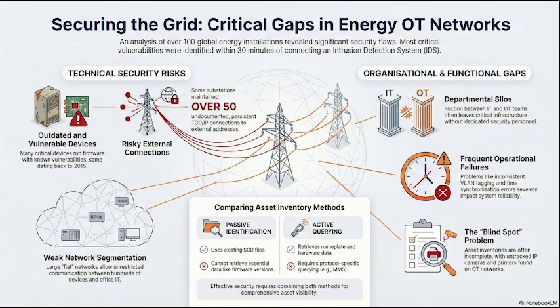If a blackout happens, you need to know the exact sequence of events: device A tripped at this millisecond, device B tripped 3 milliseconds later. But they found devices in the wrong time zones or using default timestamps. So if you're trying to investigate a crash and one device thinks it's 2026 and another thinks it's 1970, you're flying blind—you can't reconstruct the event.